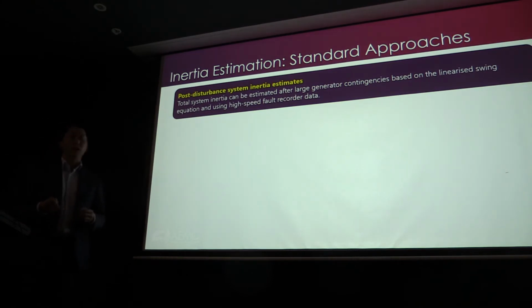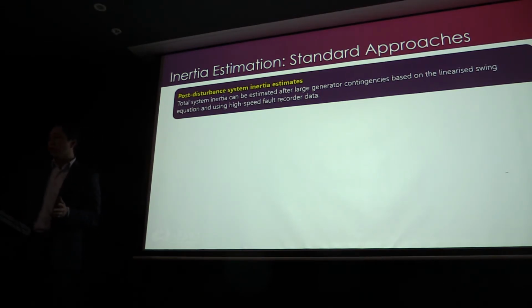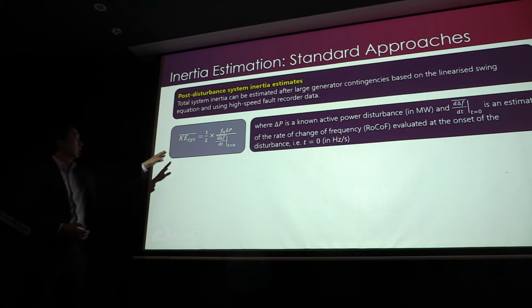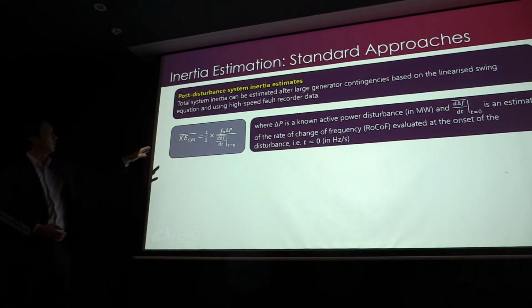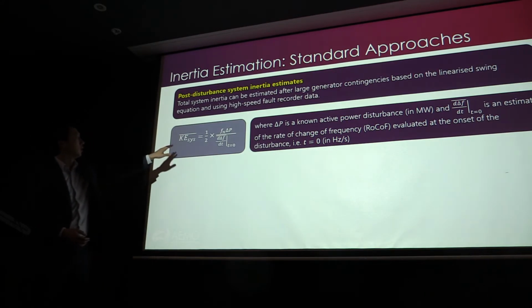So the other way that you can measure inertia, the most common other way, is after a disturbance. Once a generator trips, for example, you can get all the high-speed traces, and you can try to estimate what the inertia would have been given this frequency trajectory after that trip. So you use the linearized swing equation and some high-speed fault data. So here's what the linearized swing equation looks like. Not very good on this screen, but here's the inertia estimate.